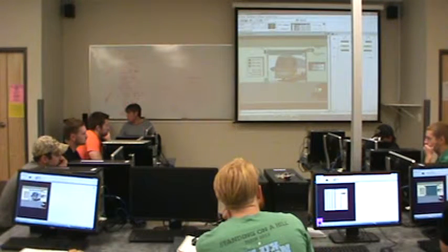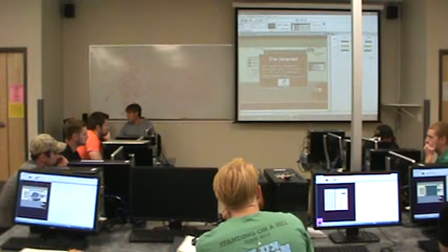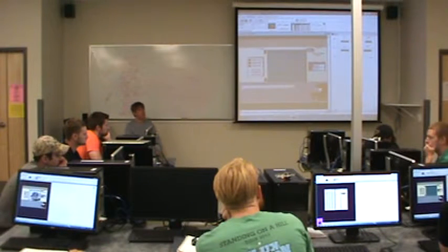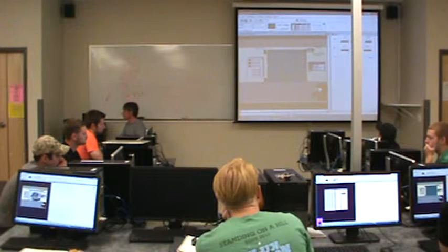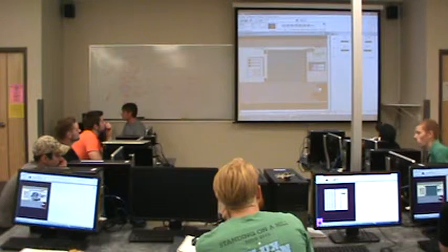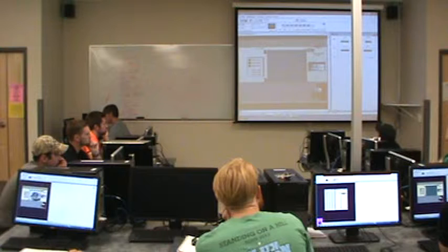See? That keeps me from burning the motor out. I can still burn the motor out nicely by hitting the close button and holding it down. Okay? So what do I need to do? I need to use the lower limit switch in the same fashion. So let's just try putting in a set of contacts, just like I did at the top, to see if that works. Okay? Put the address and I'll label it lower limit.